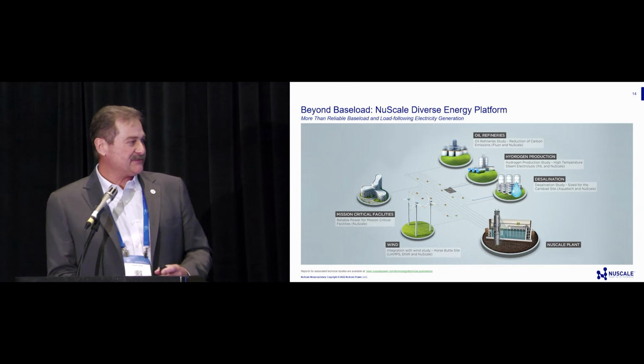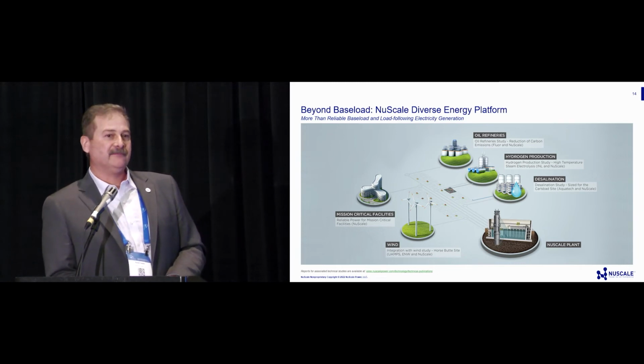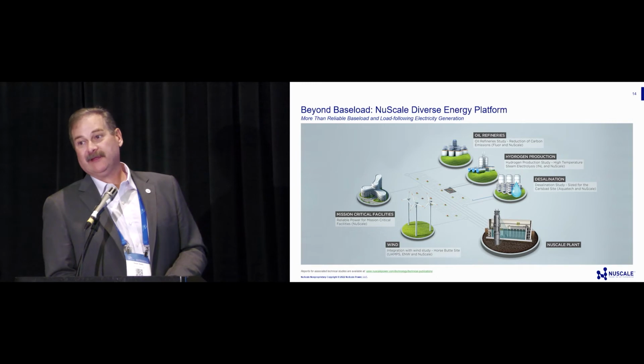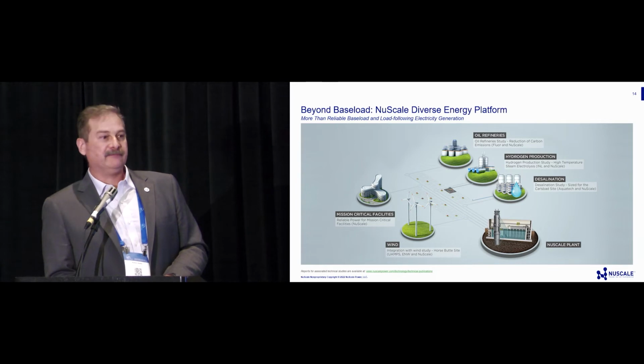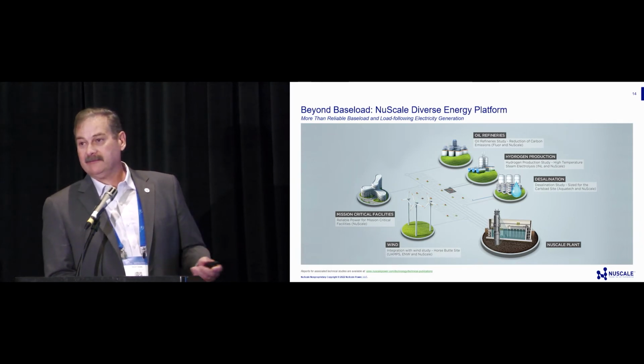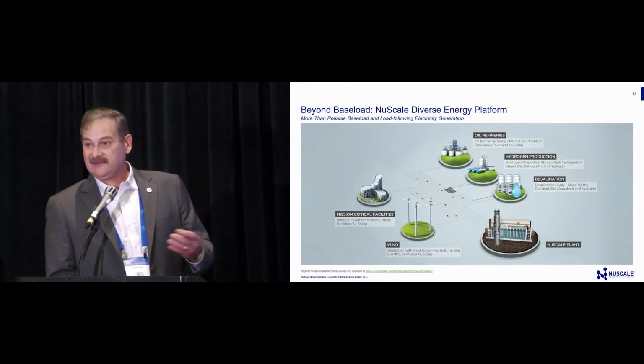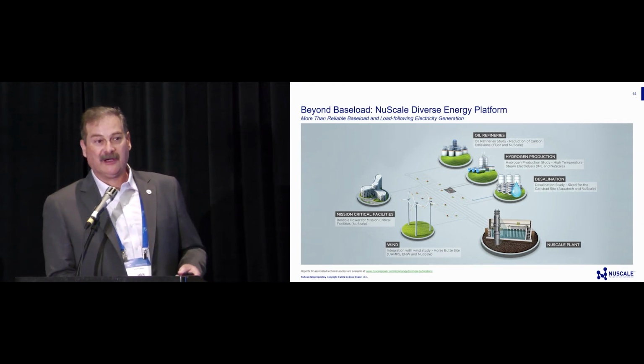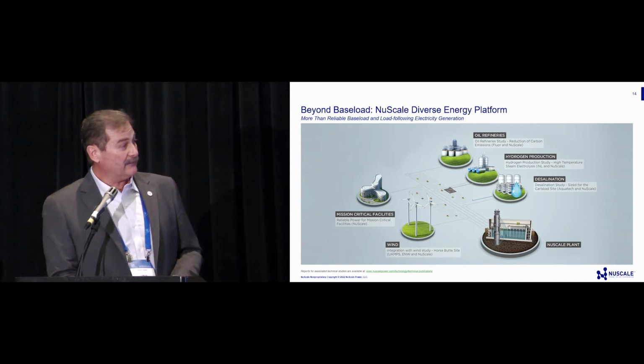Beyond base load, mission critical facilities, we're designing to be very friendly with wind and solar as far as ramping rates for electrical generation. By being smaller reactors, we can ramp reactor power fairly quick, and if we need to ramp more electrical load, we can always bypass steam around the turbine and ramp electrical load faster than what the reactor would need to be. And the same thing, if you're raising power, you could have the reactor at 100% power and you could stop bypassing steam, putting more steam through the turbine and ramp up your electrical output faster than the reactor could do a power ascension.